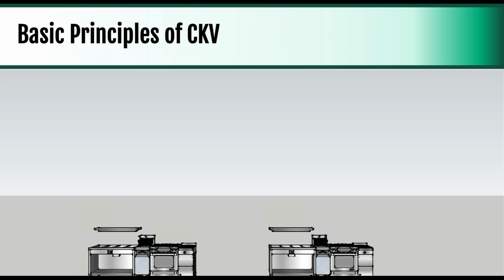So the basic principles of commercial kitchen ventilation: when we design a kitchen, everything starts with the appliances. We do that because technically, when you look at NFPA 96 or UL listings, they go by appliance temperature to determine air volume. We know that even though an oven is a 400-degree appliance and a range is a 400-degree appliance, they both output very different amounts of smoke and effluent. And so because of that, we always get the appliances to determine our air volumes.